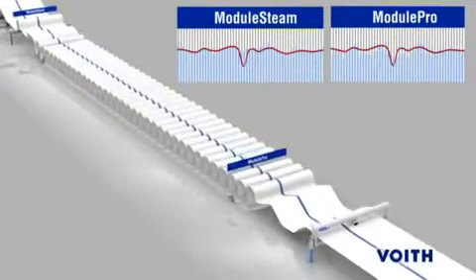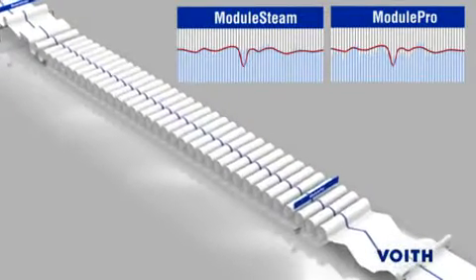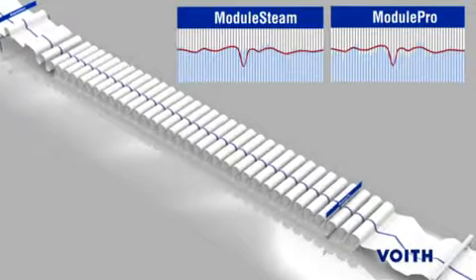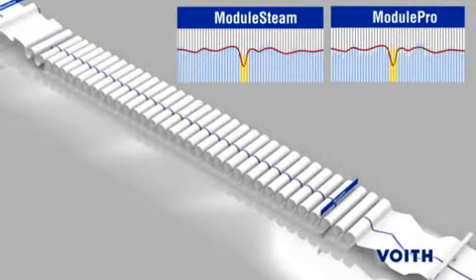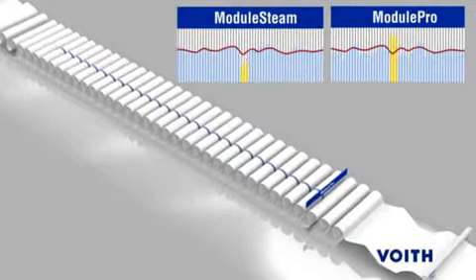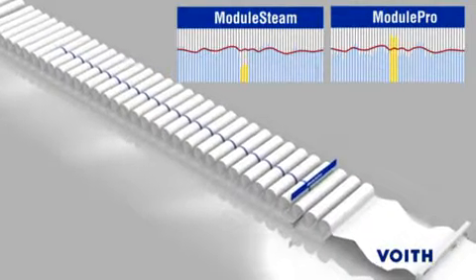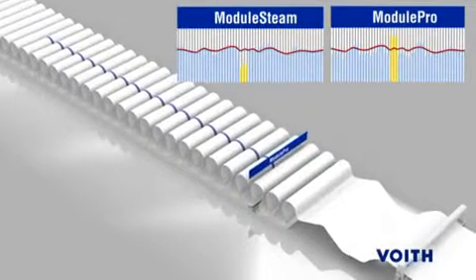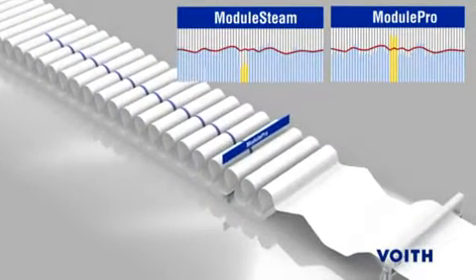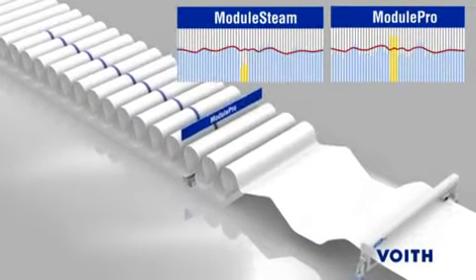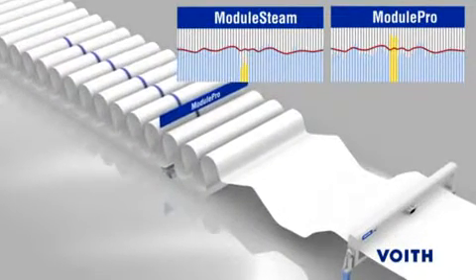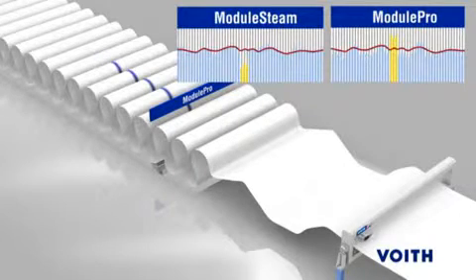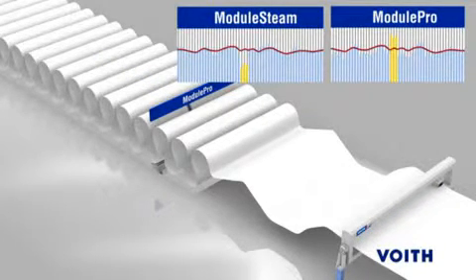The OnQ Profimatic control software combines the individual actuators into a total solution, so that an overreaction cannot occur in the control. With the feed-forward control, the subsequent actuator already knows what the control behavior of the upstream actuator was and adapts its own behavior appropriately. Thus, additional controls are avoided. The feed-forward control is another strength of the OnQ Profimatic.